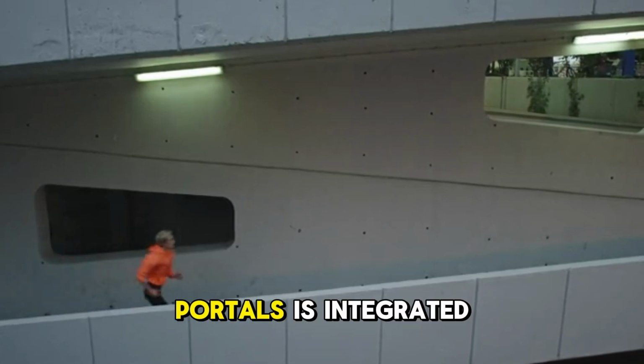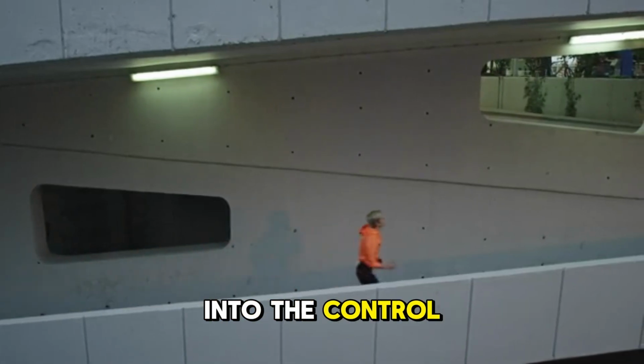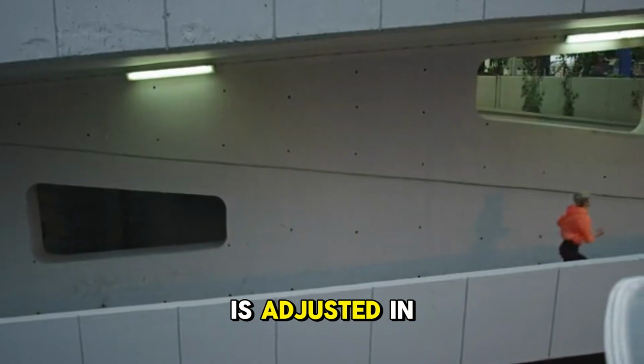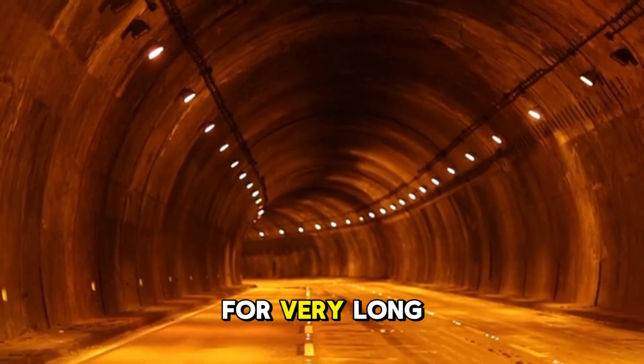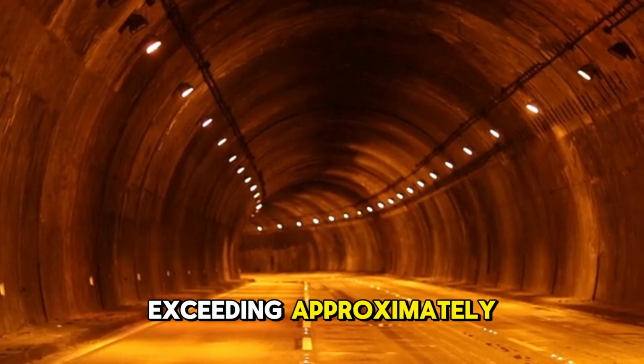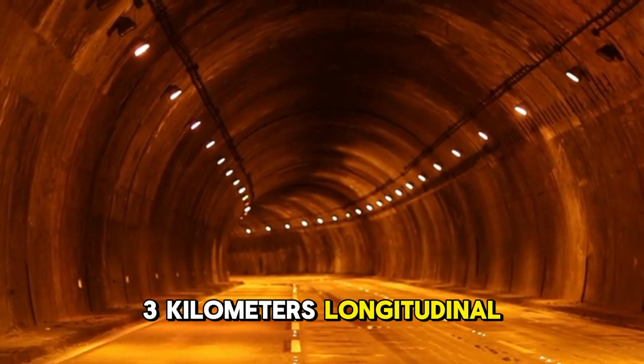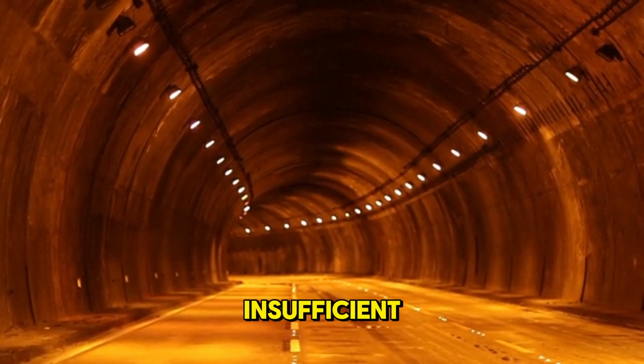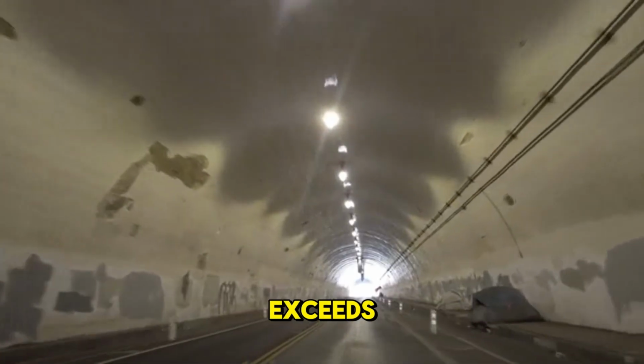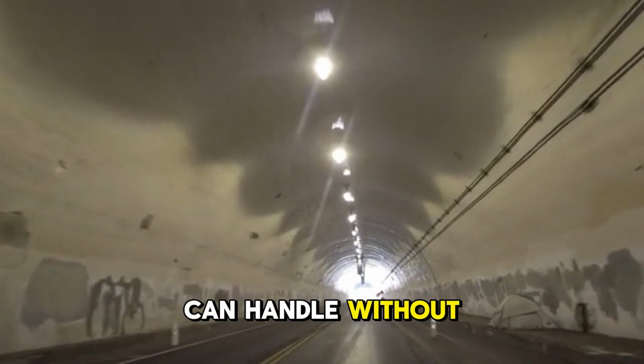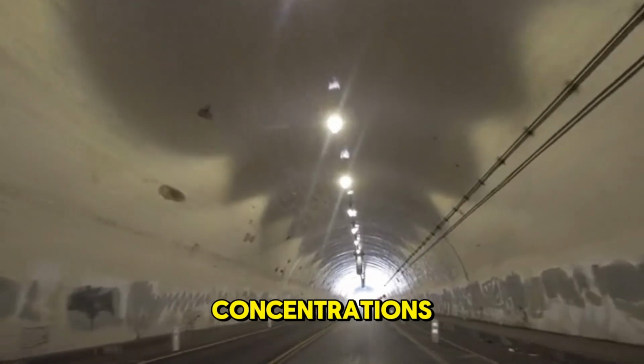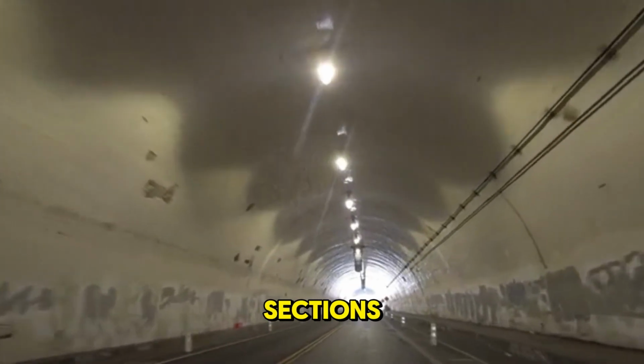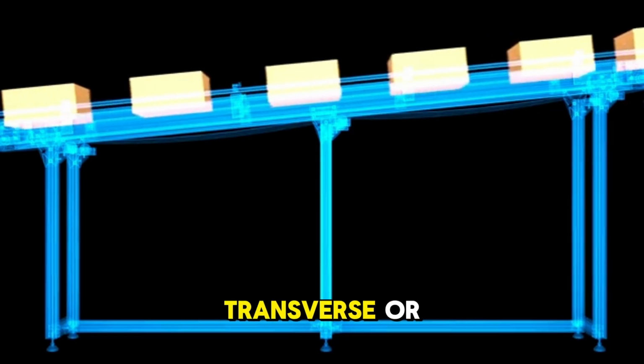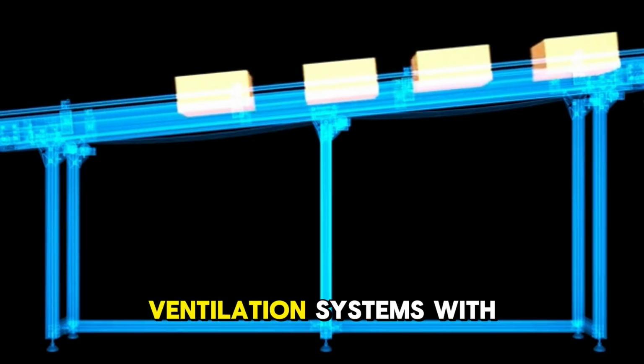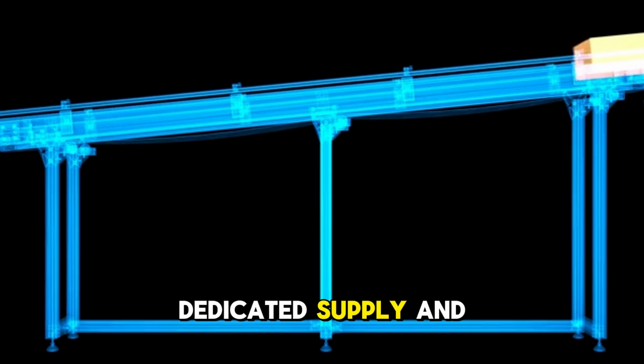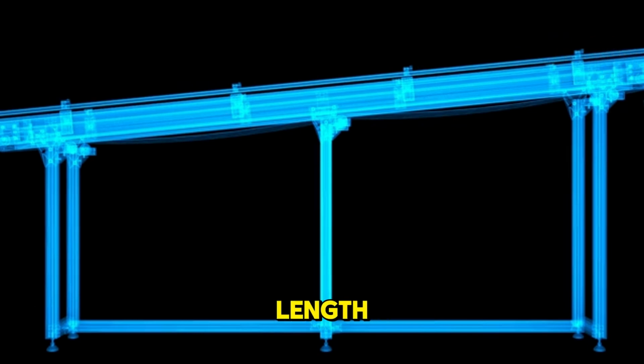Meteorological monitoring at the portals is integrated into the control system, and fan operation is adjusted in real time. For very long tunnels, those exceeding approximately 3 kilometers, longitudinal ventilation alone becomes insufficient. The contaminant load exceeds what portal exhaust can handle without generating unacceptably high concentrations in the middle sections. These tunnels require transverse or semi-transverse ventilation, systems with dedicated supply and exhaust ducts running the full length.